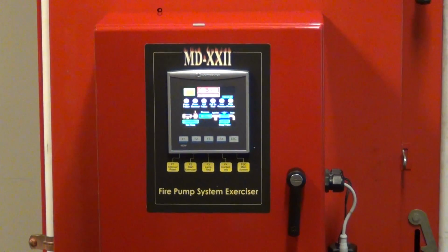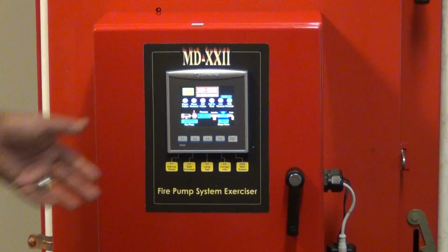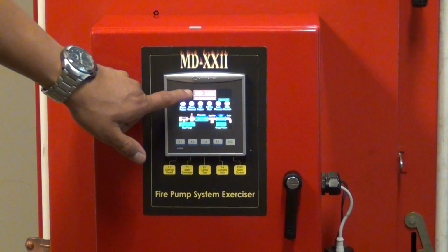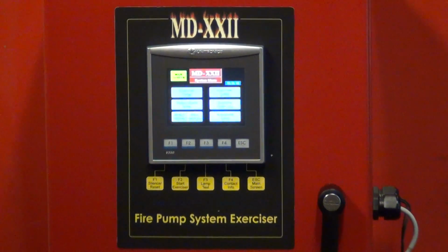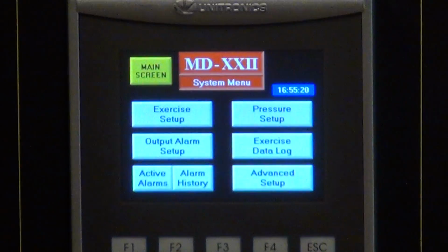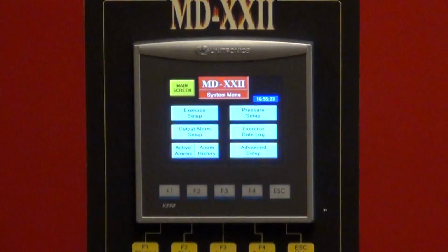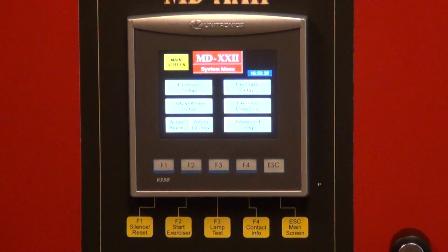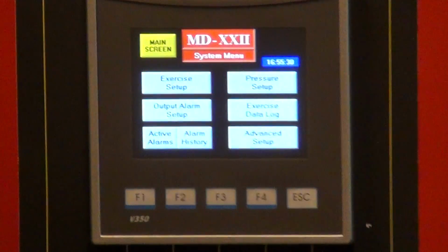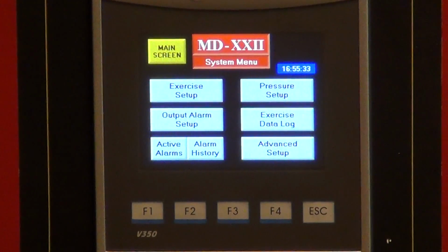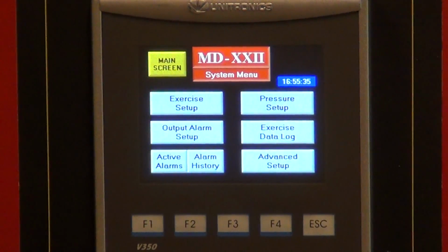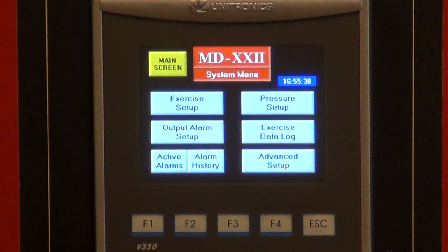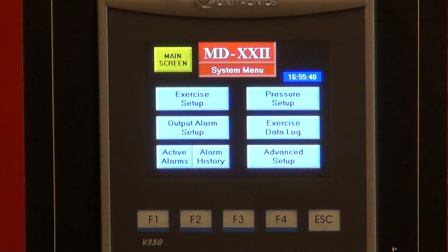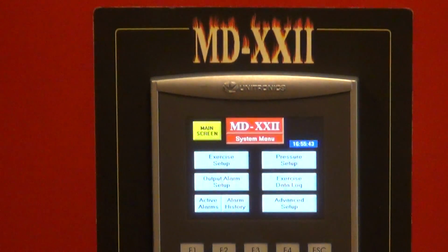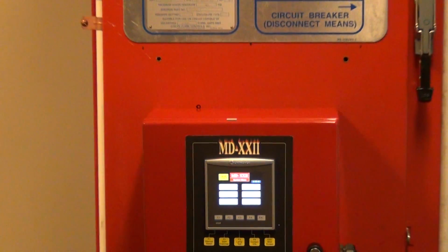The MD22 is a fire pump system exerciser that offers the ability to exercise your fire pump on a weekly, monthly basis, or even as often as every day. By simply navigating through the touch screen, you can get to your exercise. The MD22 also offers your output alarms to be enabled or disabled. When I say output alarms, you're talking your fire pump running, power failure, phase reversal, coil failure, fail to start, high and low pressure alarms.